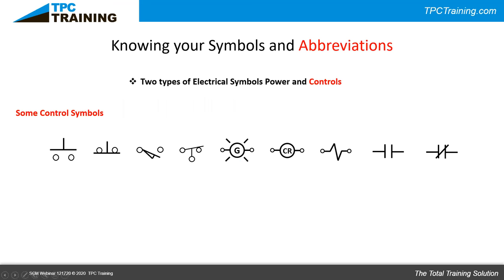In controls, we have lots of different symbols. A normally open push button (abbreviation NO) is a momentary switch — when you push it and let go, it opens again. Think of a green start button for a motor. A normally closed push button (NC) is also momentary — this would be the stop button on a motor, or an emergency stop button, which typically has a mushroom-type head.